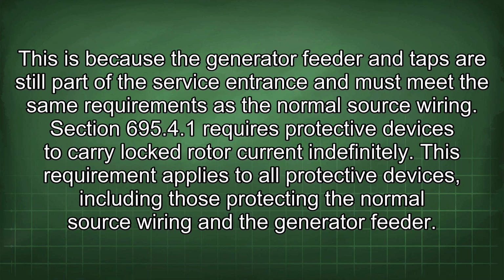Section 695.4.1 requires protective devices to carry locked rotor current indefinitely. This requirement applies to all protective devices, including those protecting the normal source wiring and the generator feeder.